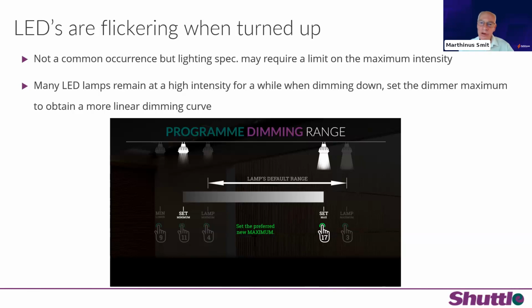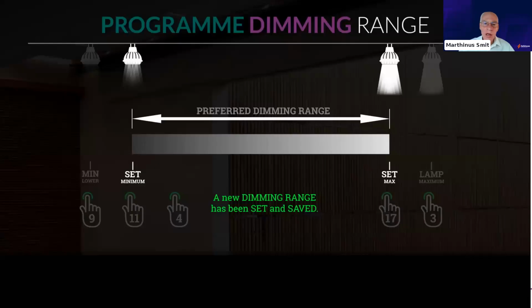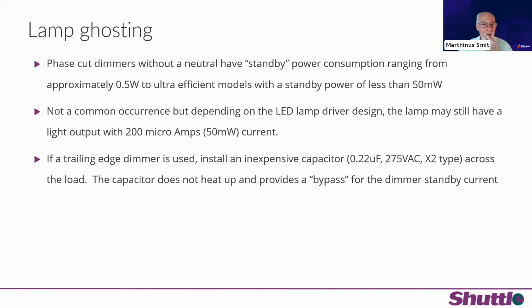So in the case of the non-linear lamp, you can start dimming down until you visually see that the lamp starts dimming, and then just set your maximum intensity. That makes the dimming curve much more linear. So ideally, you must be able to set your whole dimming window of your dimmer, and that addresses the maximum intensity, minimum intensity, lamp flickering, and so on.